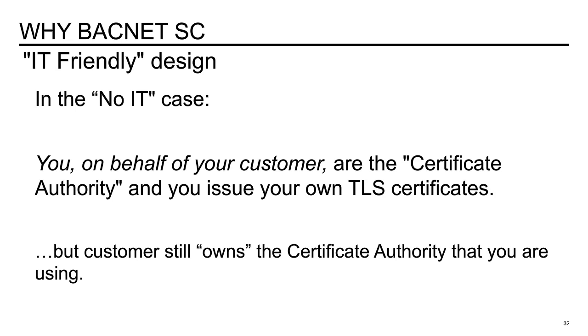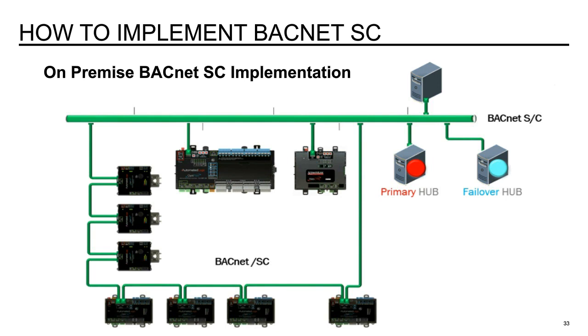So now I want to take a few minutes and let's talk about how to implement BACnet SC. On your screen right now is a new implementation of BACnet SC with everything in the facility. You can see you have the BACnet SC devices using the BACnet SC protocol, which is in green, and then a primary hub, a failover hub, and then the server that's managing whatever system, whether it's a building automation system or lighting system. A couple things I want to point out here. These primary hubs and failover hubs could be a physical piece of hardware, or they could be a software device as well. It doesn't necessarily have to be a physical piece of hardware. But you can see it resides on the network, and it talks BACnet SC.